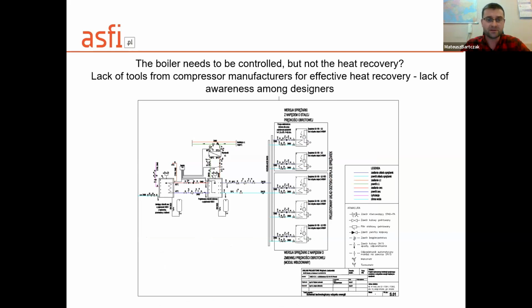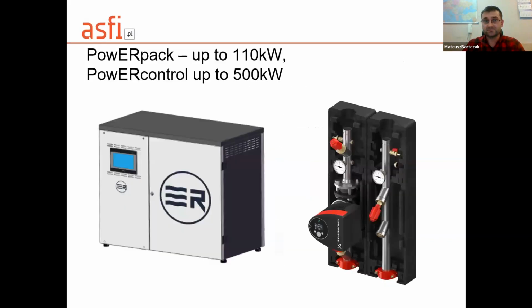You cannot give a customer a heat exchanger and leave him to deal with it himself. You can't leave the designer without support on how it should work. On this project, the designer didn't trust the compressor supplier. The designer designed variable speed pumps, the linear valves on the water side, and reduced them to a rectangle with a dashed line, on which he wrote PLC. He didn't know how to control it. But the project was prepared mechanically so that if someone knew how, they could use it.